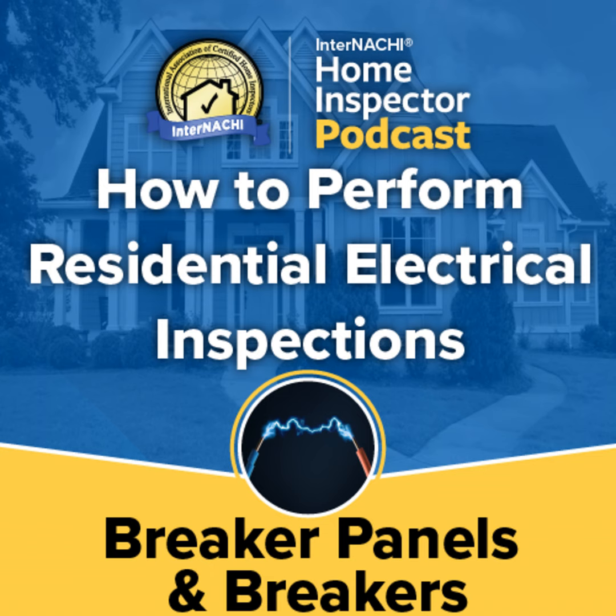AFCI breakers. Arc fault circuit interrupters, or AFCI breakers, have been required in new construction since the 1999 edition of the NEC. Many jurisdictions are now observing recent code additions which have expanded the use of AFCI devices to almost everywhere within a dwelling. These breakers are designed to trip if they sense arc faults in the circuit, which are caused primarily by damaged wiring. What is an AFCI?